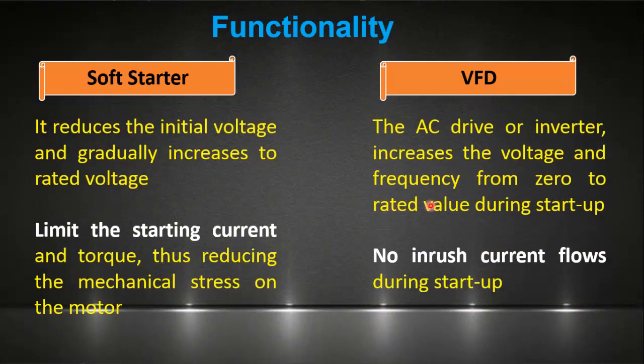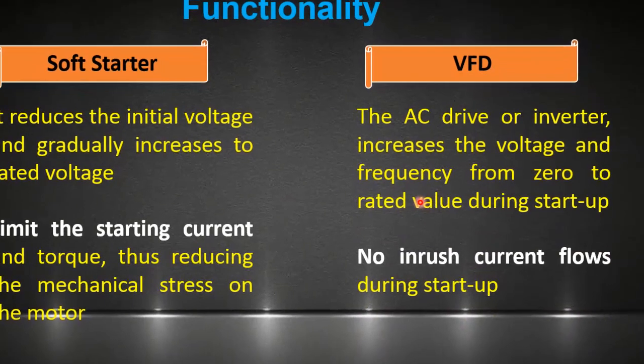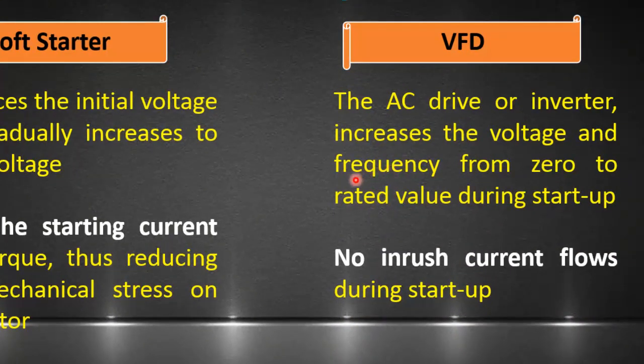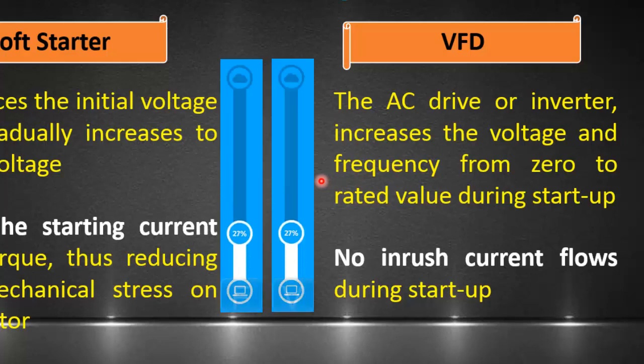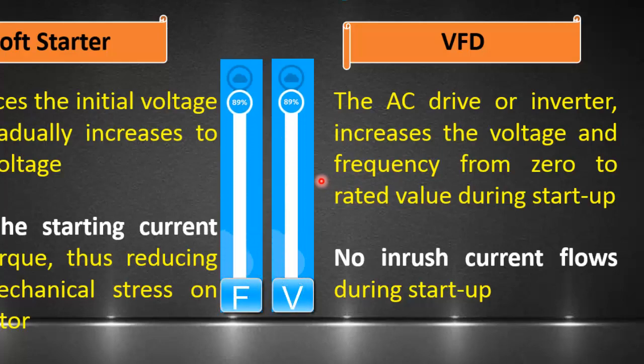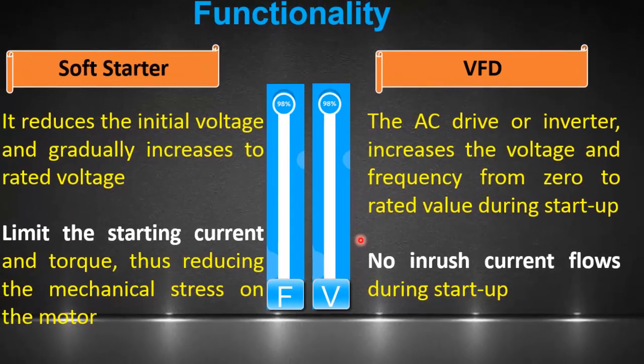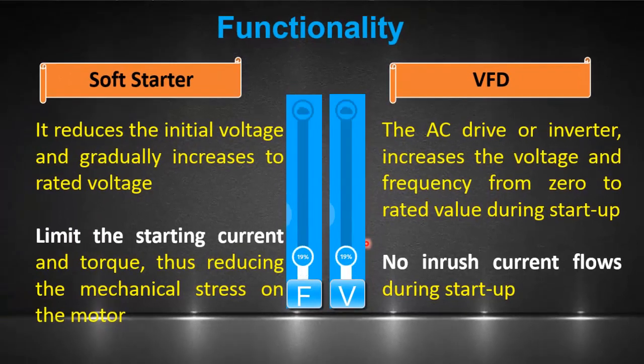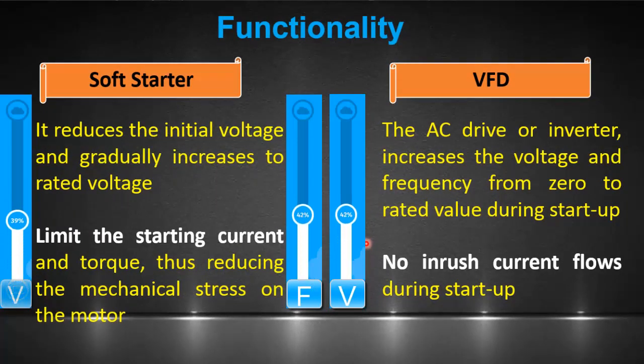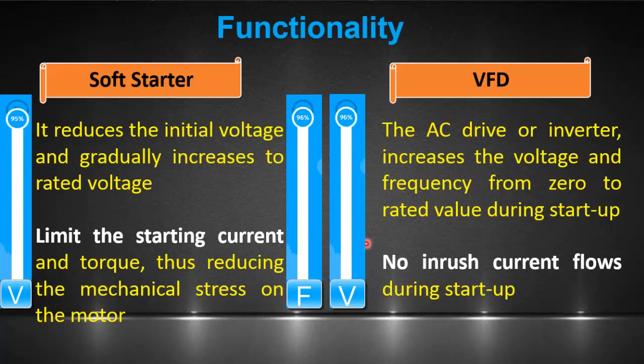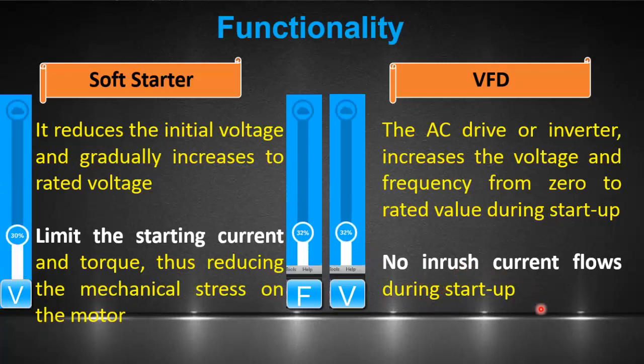A VFD, also known as an AC drive or inverter, is a device that controls the speed and torque of an electric motor by varying the frequency and voltage simultaneously supplied to the motor. The main difference is that a soft starter only controls the voltage, while a VFD controls frequency and voltage both at the same time. Therefore, almost no inrush current flows during starting of the motor.